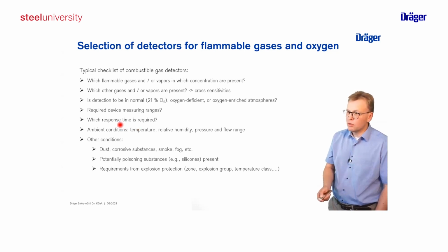Response time, for example: with this principle, a catalytic bead sensor can take up to 30 seconds before you get your alarm. You need to consider this if you have any kind of measures which should be activated. We need to consider ambient conditions, temperature, pressure, etc., but also the atmosphere around. Dust, poisoning substances, etc., have an impact on selecting the right sensor, but also maybe on using accessories to protect the sensor itself.